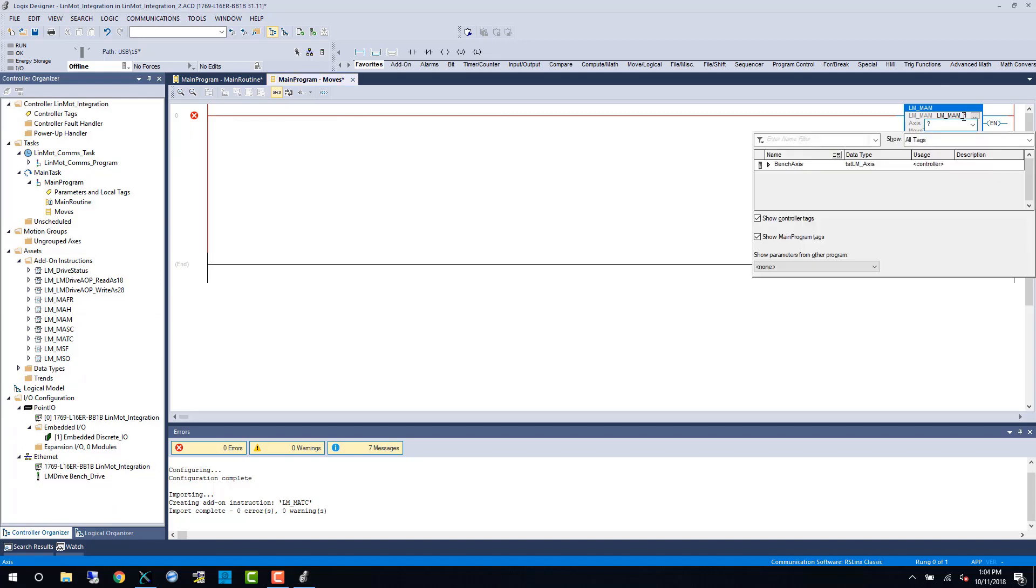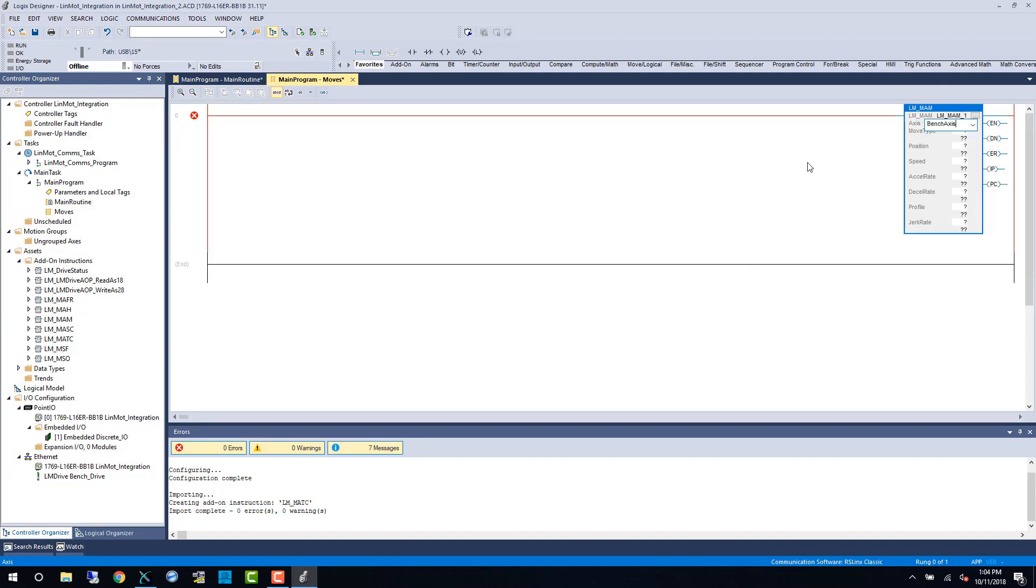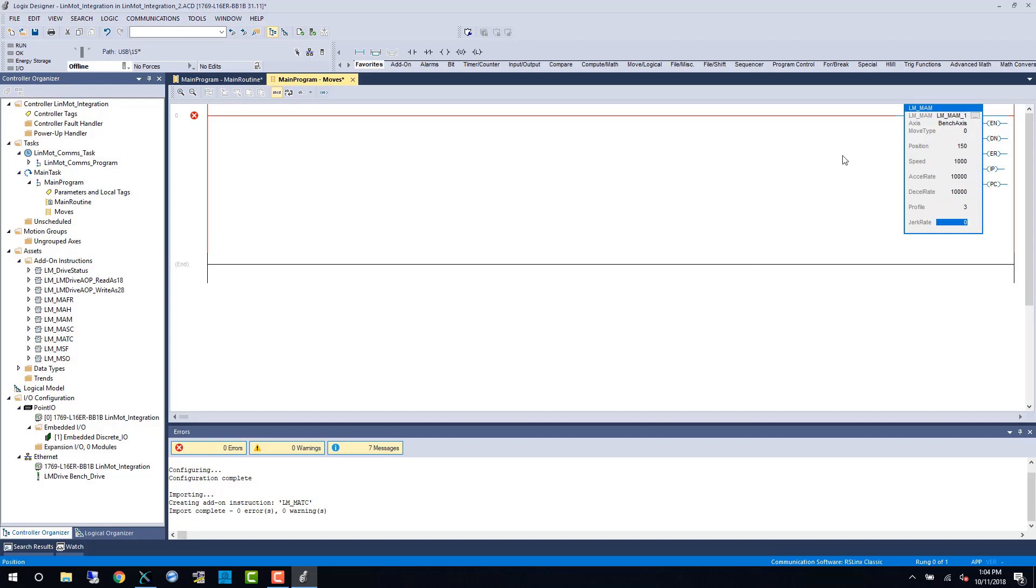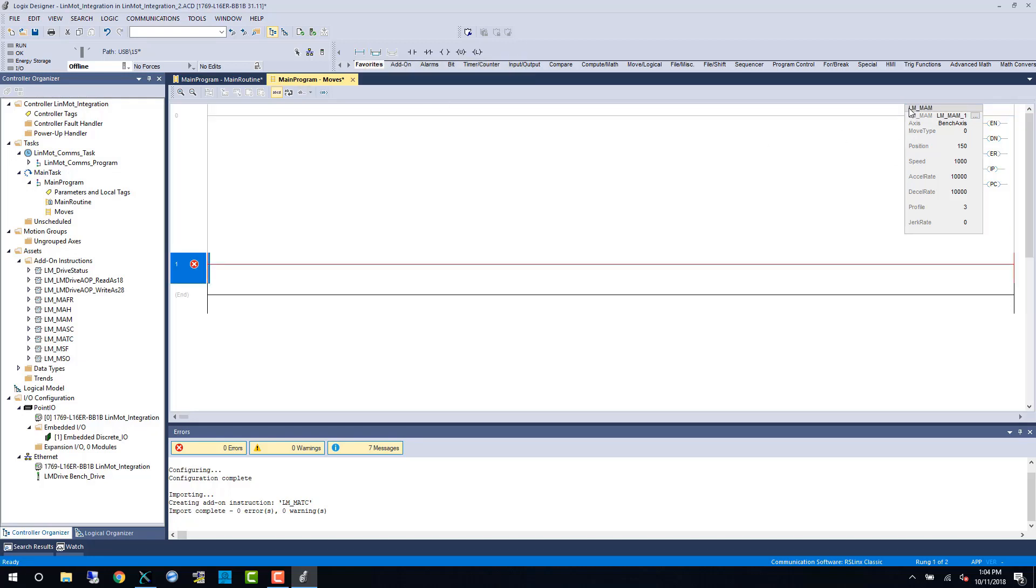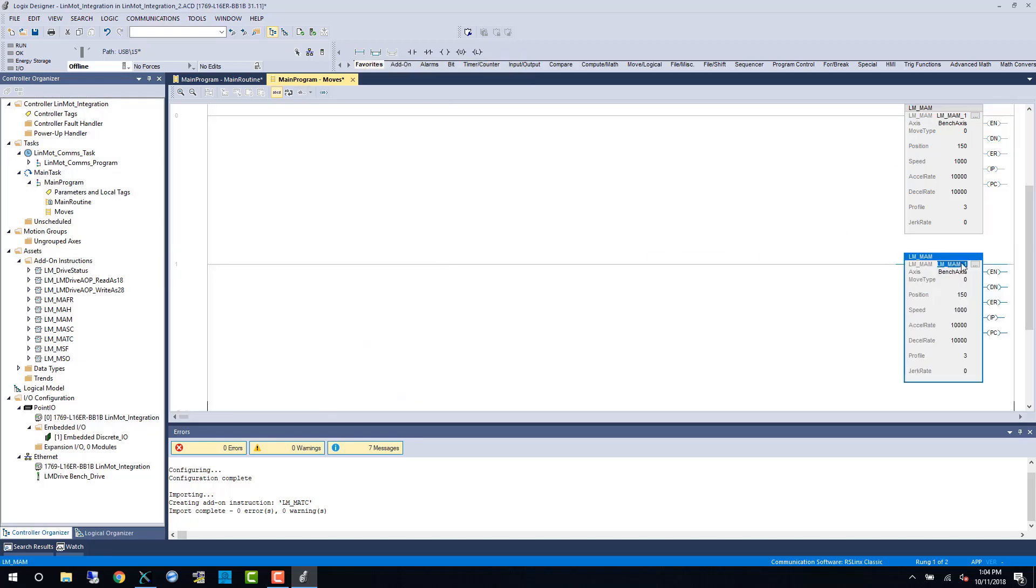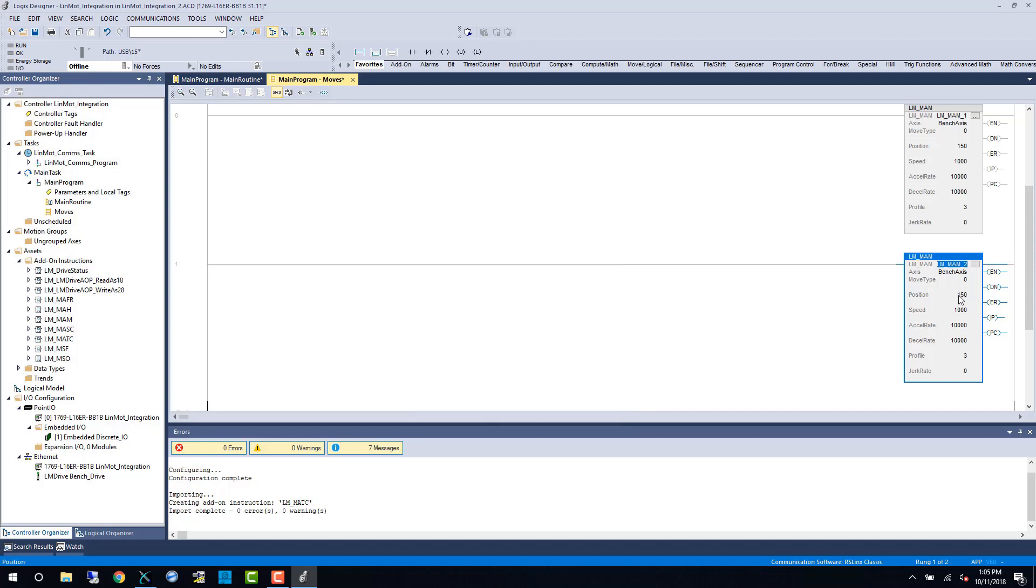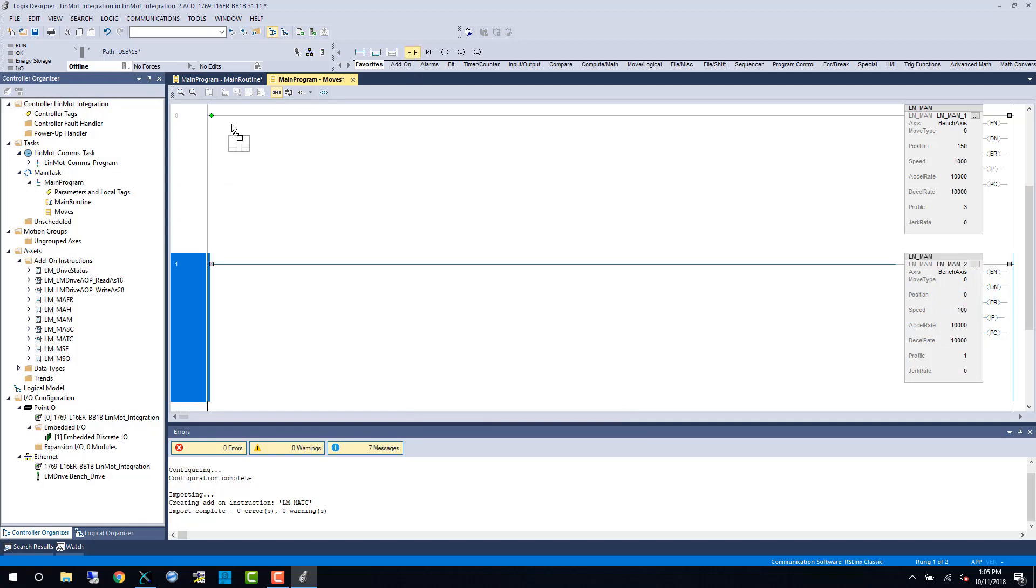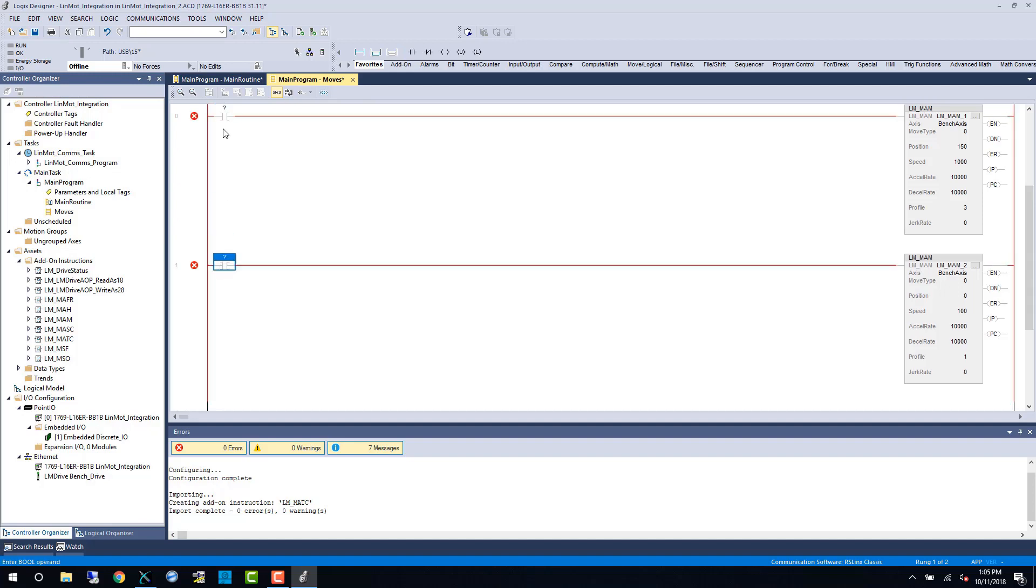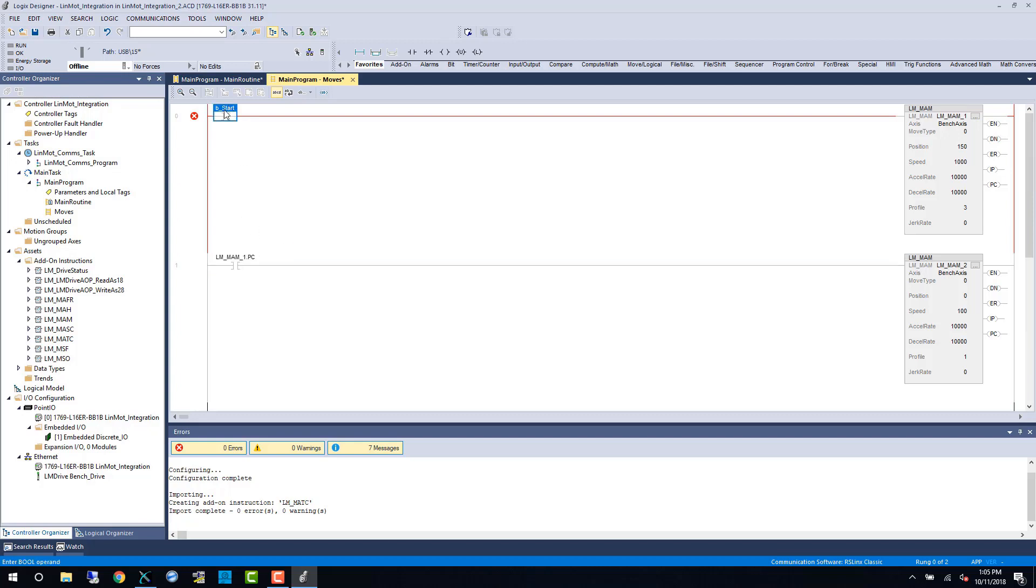The first AOI we see in action is the MAM command, and this is structured similar to the native MAM command in that we have a move type of 0 for absolute, 1 for incremental, a position which is going to be a distance in millimeters, a speed in millimeters per second, and an acceleration and deceleration rate of millimeters per second squared. Lastly the profile, 3 represents a sine move in our first block, and 1 represents a trapezoidal move.